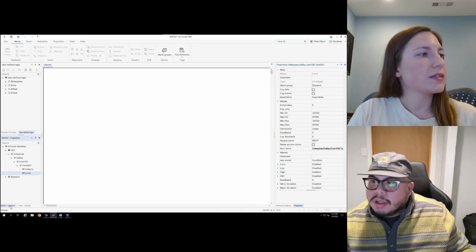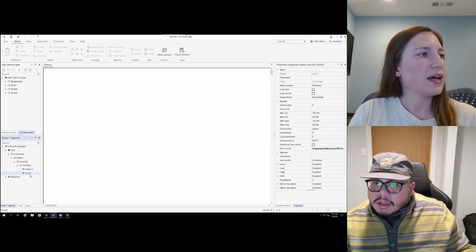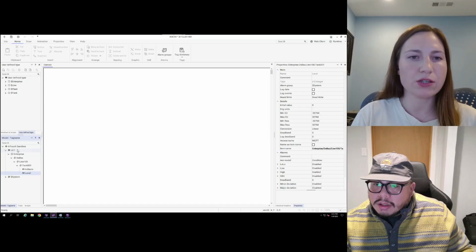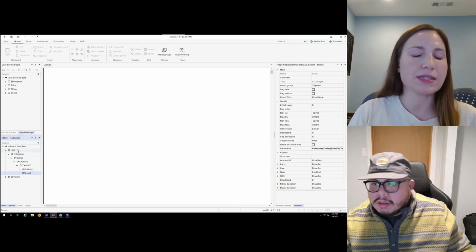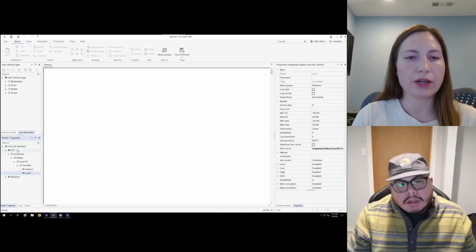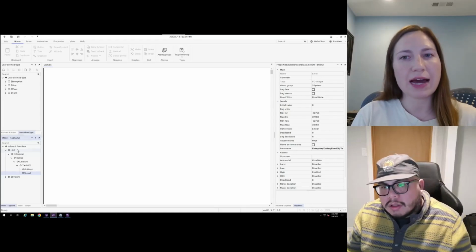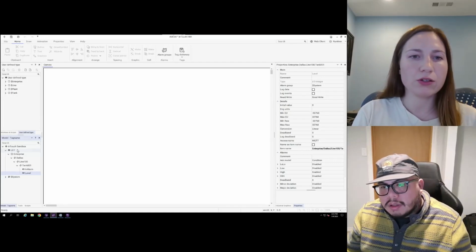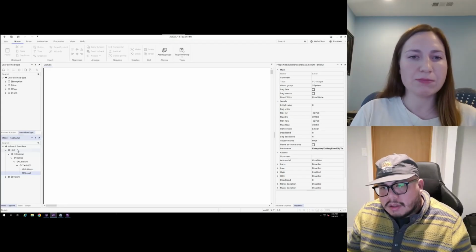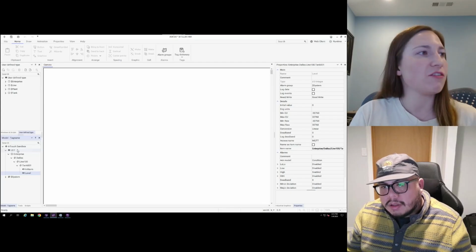Yeah. So in my InTouch application here, I created this UDT to demonstrate this. We had a previous podcast on UDTs, and in case anyone missed that podcast, basically a UDT allows me to create an object-oriented hierarchy for my tags in InTouch. If you compare UDTs to the traditional tag name dictionary, that tag name dictionary is really a flat tag structure. These UDTs allow me to have more of a hierarchy, as you can see here.